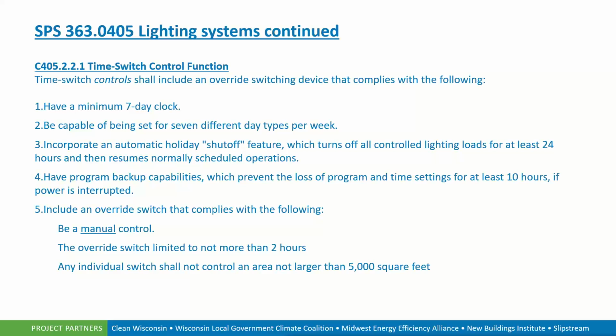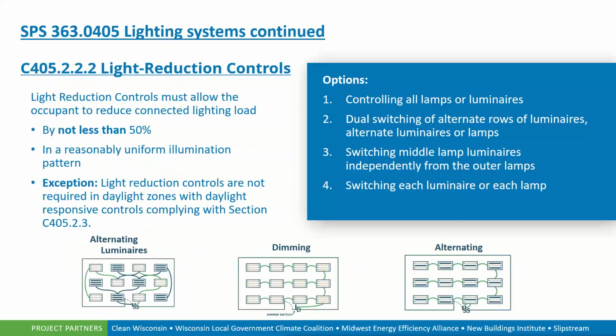So time switch control function is significant for lighting within the commercial buildings, as well as our light reduction controls as outlined in section 405.2.2. Again, this is something that the light reduction controls must allow the occupant to reduce the connected lighting load. As you can see, there are different methods where we can have alternating luminaires, we can dim lights, we can have alternating light fixtures illuminated. And there's some exceptions for that, but they're not required in daylight zones with daylight responsive controls that comply with the next section of the code. And again, some of the options that I talked about: controlling all lamps or luminaires, dual switching of alternate rows, middle luminaires independently of the outer lamps, and switching each other or every other light fixture. Again, you need to refer to the code section for any additional exceptions for this. It's a little bit lengthy to place in here.